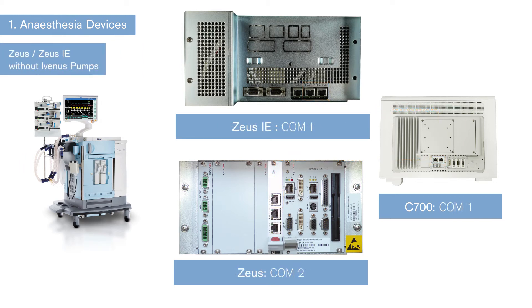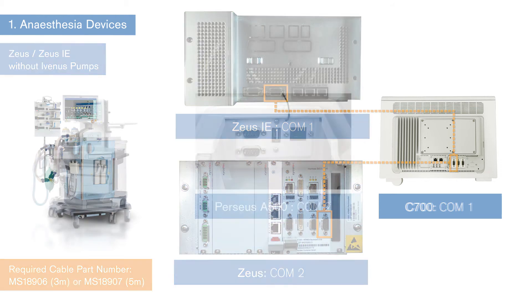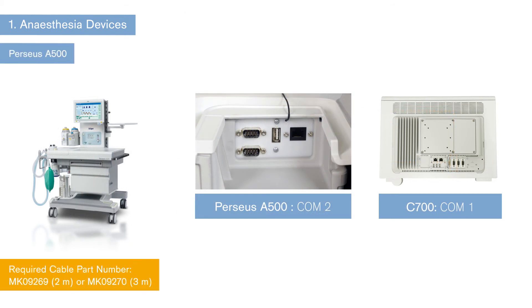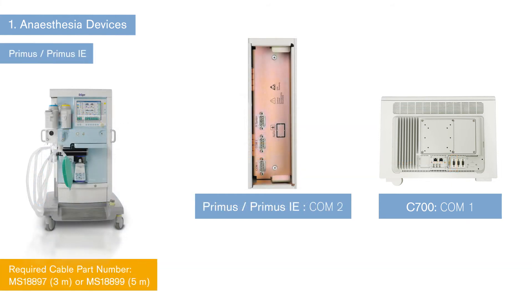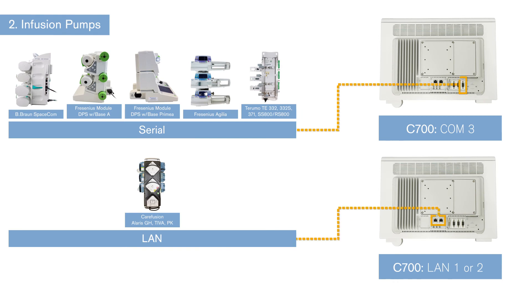In case of Zeus and Zeus IE without iVenus pumps, serial connection is used. Zeus IE COM1 and Zeus COM2 will be connected to SmartPilotView. In case of Perseus A500, COM2 port will be connected to COM1 of SmartPilotView. In case of Primus and Primus IE, COM2 will be connected to COM1 of SmartPilotView. For infusion pumps, depending on the brand, serial or LAN connection will be used to connect to SmartPilotView.